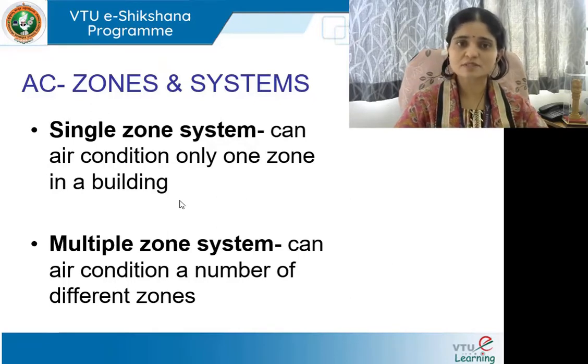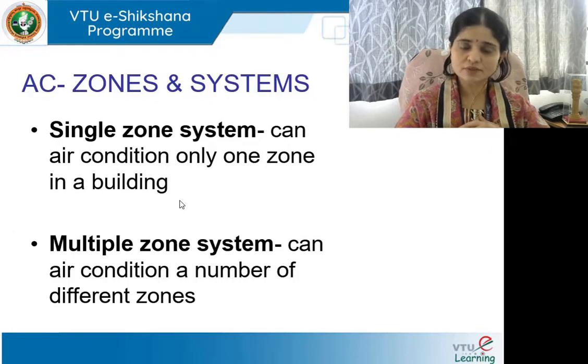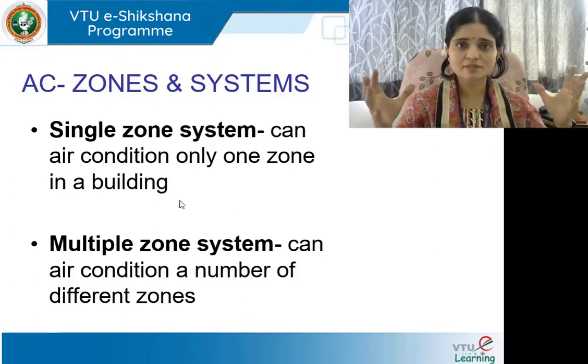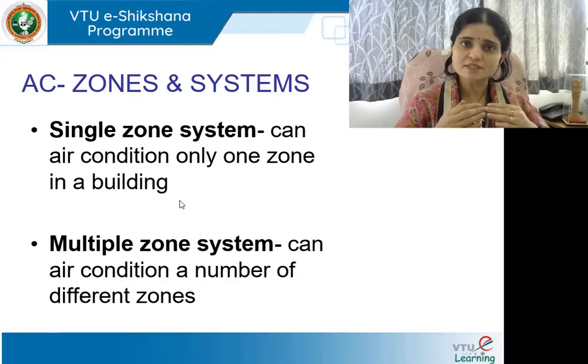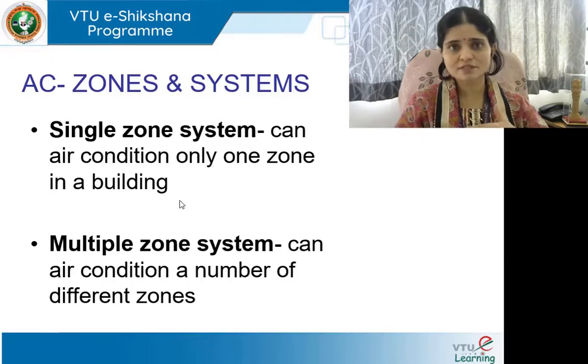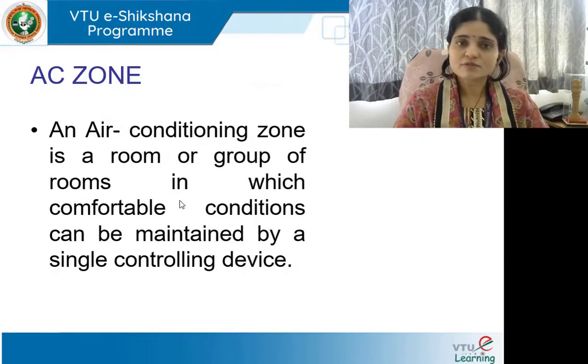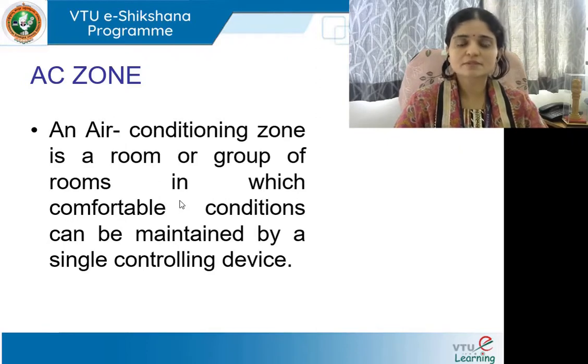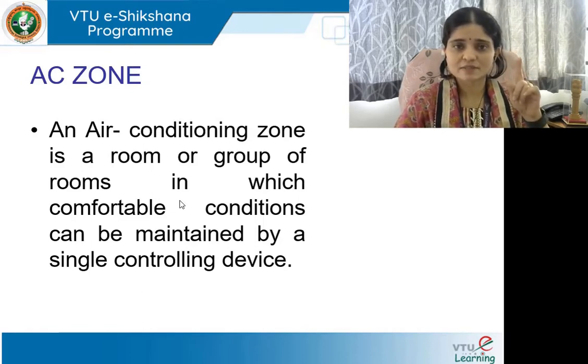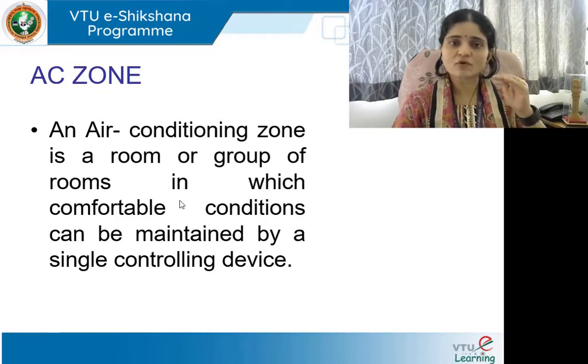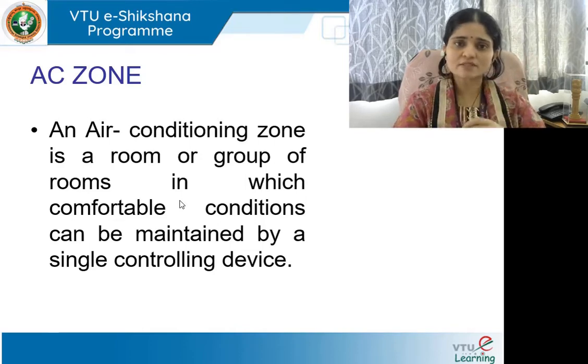Zoning the building as per the load requirement is essential. A lecture has been conducted on this previously in Module 1. Based on the cardinal directions — north, south, west, east — and the activity in that zone or set of spaces, zones are created. If we do this exercise at the concept stage itself, the building is going to be compatible with the HVAC and energy efficient. An air conditioning zone is a room or group of rooms in which comfortable conditions can be maintained by a single controlling device, hence collectively called a single zone.